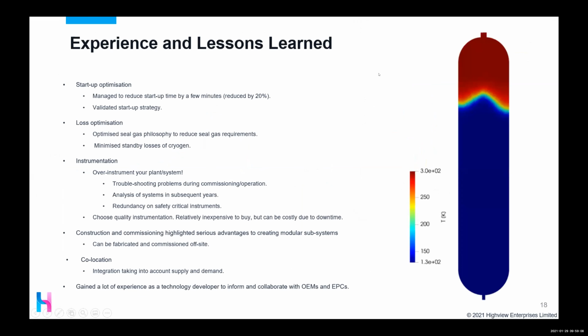Finally, just to talk about experience and lessons learned. One of the main benefits we got out of this system was a lot of the validation work we were able to do with our models on our high-grade cold store system and our thermal storage system. The graphic on the right is a bit old now, but it's an early CFD modeling we carried out on the high-grade cold store. We were able to match up the experimental data with our models to ensure that we could capture the propagation of a cold front during charging and discharging to an accurate degree. We did something similar with our thermal storage system, to model the stratified tanks and to see how the thermocline within it would move.